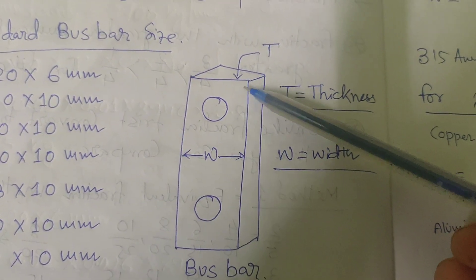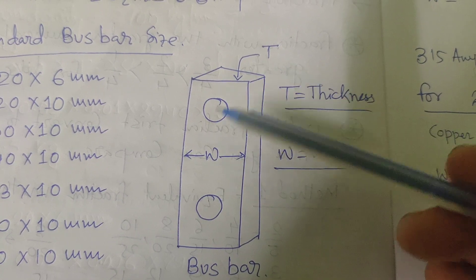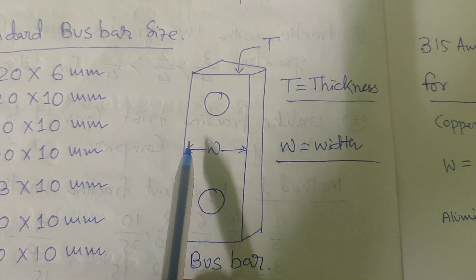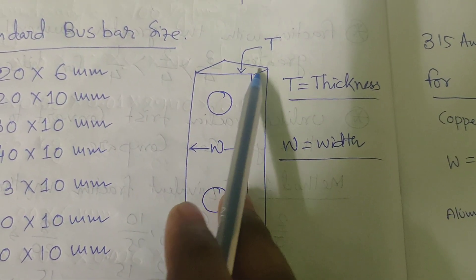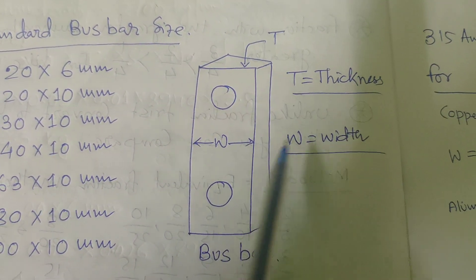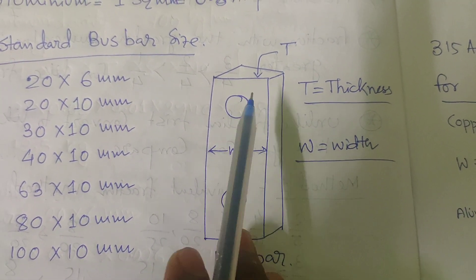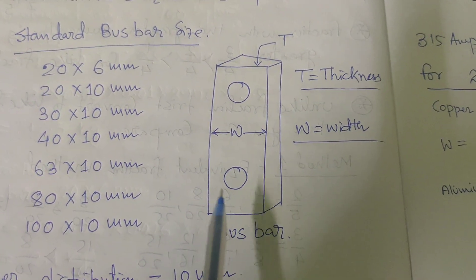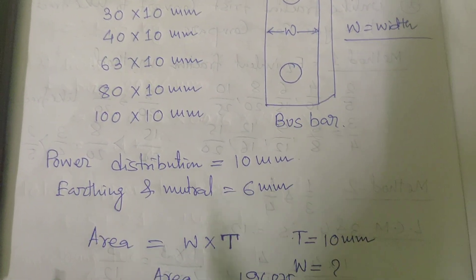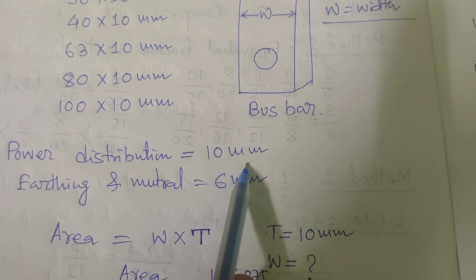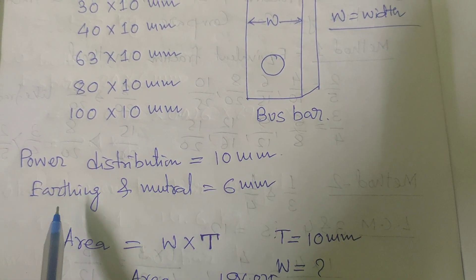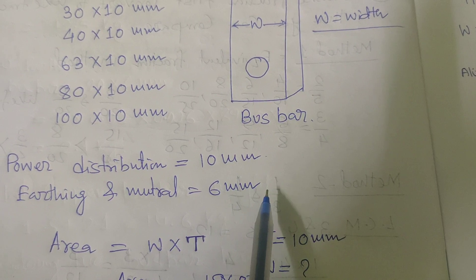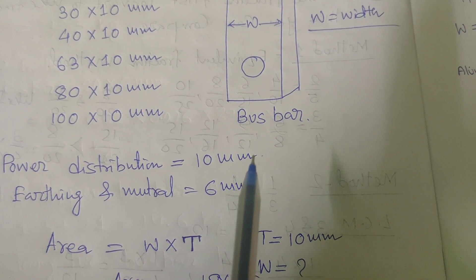Now we draw a picture of a busbar. This is the width of the busbar and this is the thickness of the busbar — T is the thickness and W is the width. These are the holes for connections with other parts of the busbars. For power distribution we use 10 mm thickness busbars, and for earthing and neutral connections we use 6 mm, 4 mm, or 2 mm as per the situation and requirement.